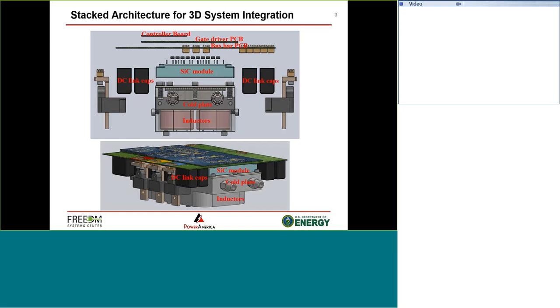The current sensors for the key phases are shown coming out here. It's a very tight integration, which was essential to achieve the target power density, and also for reducing the overall loop inductance, targeting 10 nanohenries or lower.